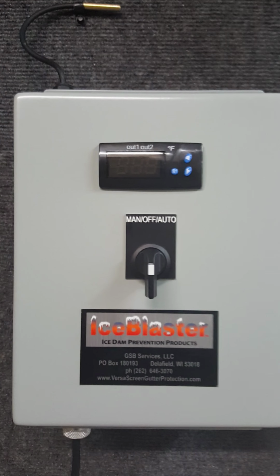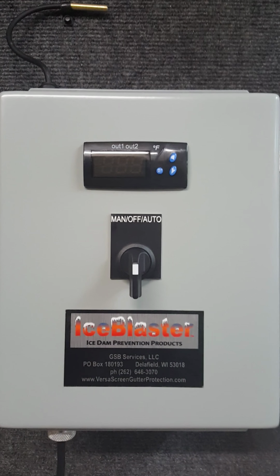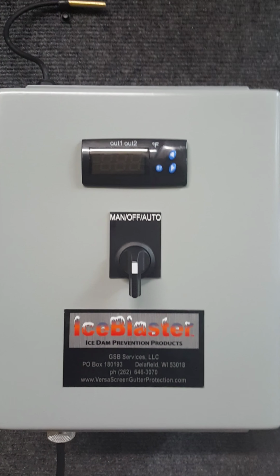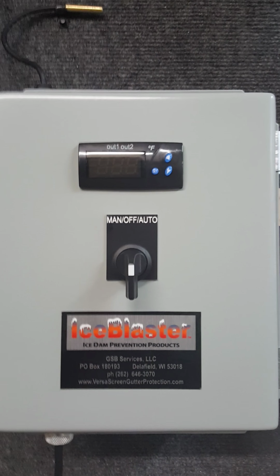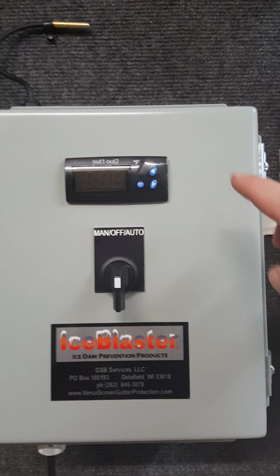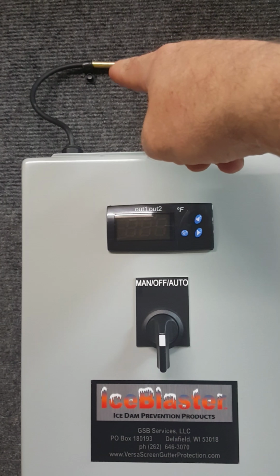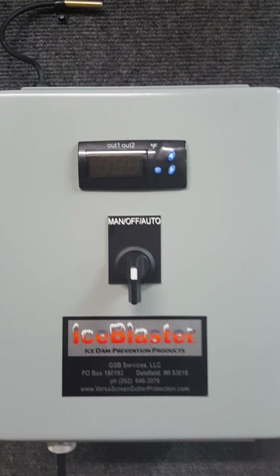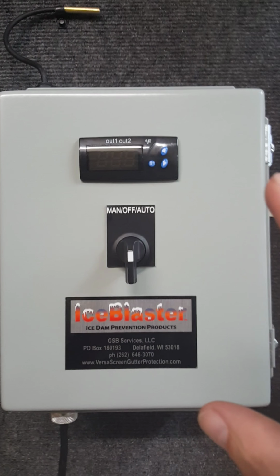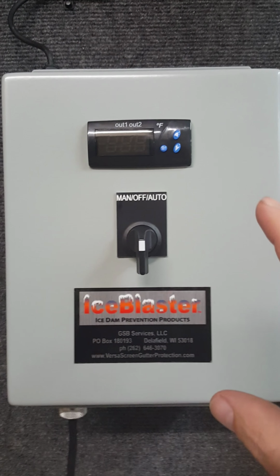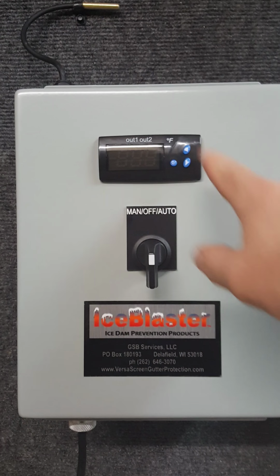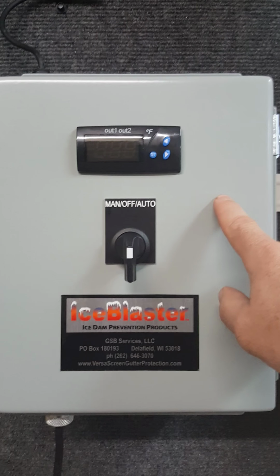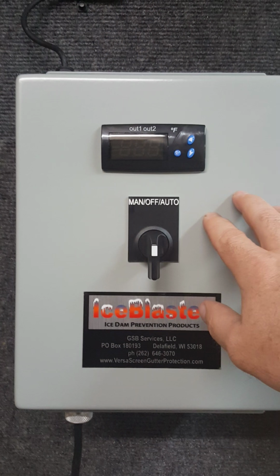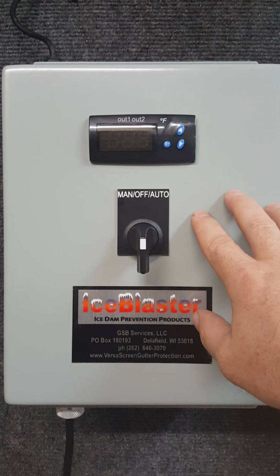Okay, so we're going to have a tutorial on the IceBlaster controller, the DCAS4. It's an ambient sensing controller based on a digital thermostat controller that measures outside temperature with a thermistor probe. One of the things you'll notice, first of all, about the DCAS4 is all of the controls are on the outside of the panel. And that keeps you safe.